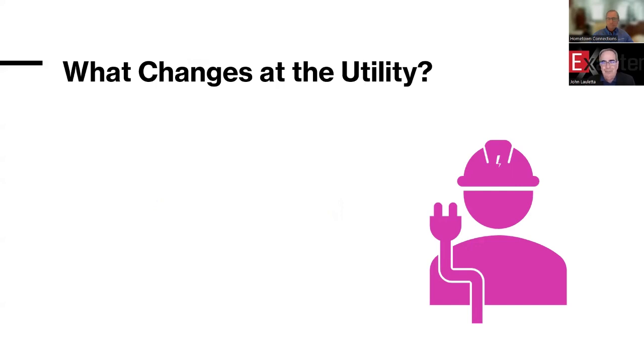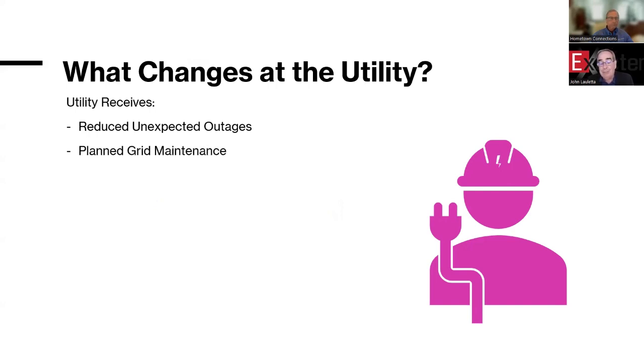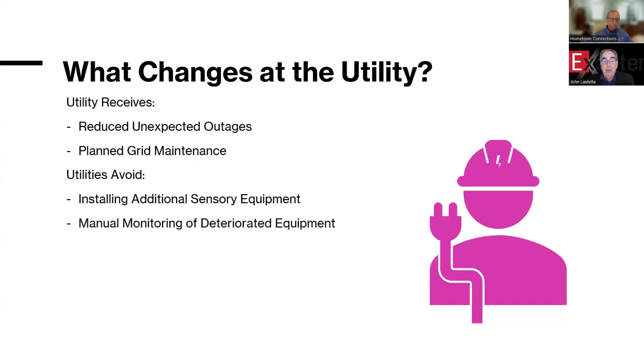So what changes for you? Well, you receive some things. You receive reduced unexpected outages. That's a good thing. You have less chance of people getting injured, less chance of outages occurring without any forewarning. You get planned grid maintenance. So now you're doing things on your schedule, not on the grid's schedule. And what do you avoid? Well, because we're talking about a mobile deployment of sensors, you avoid any additional equipment being added to the grid, which also affects grid reliability. You don't have to manually monitor any equipment for deterioration or a condition that would affect its operation.